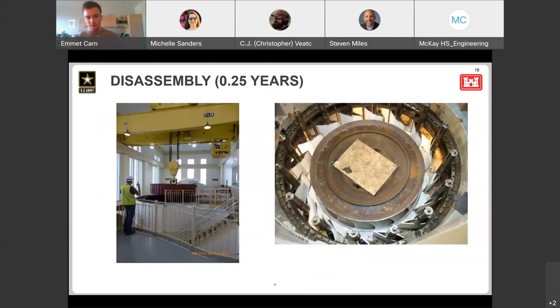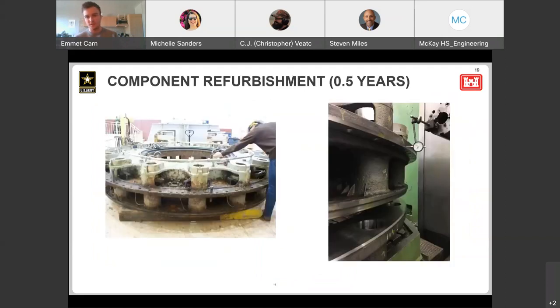Once the runners are made, we'll disassemble the unit. We have giant cranes that take off the generator and then slowly remove components of the unit—that can take a long time, disassembly is a long process. Once those components are taken out, we'll either replace or refurbish them. These are original components that have been sitting in water for a long time, so they can corrode and their surfaces can be damaged, so we decide whether to clean them up or replace them entirely.